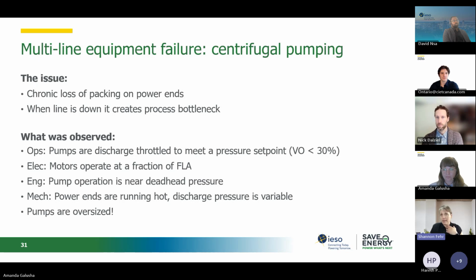In this particular case, hearing at the morning meeting over and over, we have chronic loss of packing on the power ends of this set of pumps. There were 2 lines, an A line and a B line, and each time a power end needed to be repacked, it caused a process bottleneck. So production was impacted. So we went out into the field with a whole bunch of folks and found out operations was discharge throttling these pumps significantly. The valves on the discharge side of the pumps were only 30% or less open.